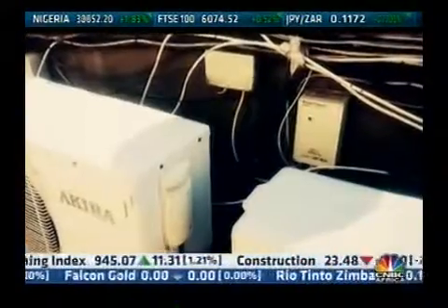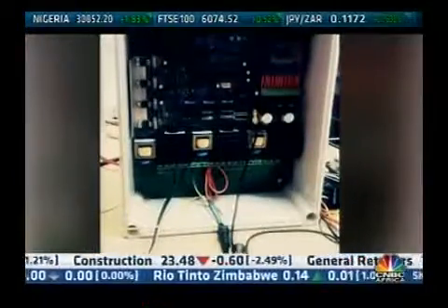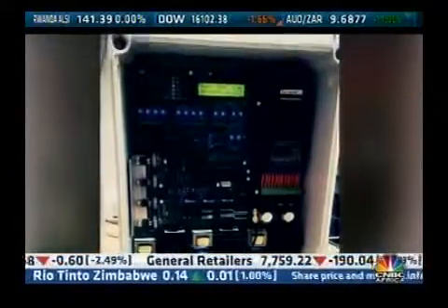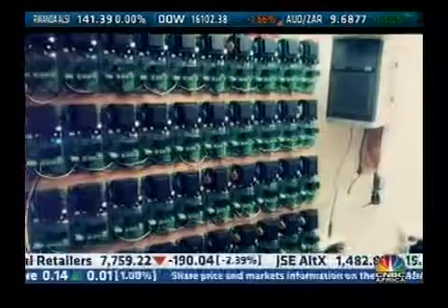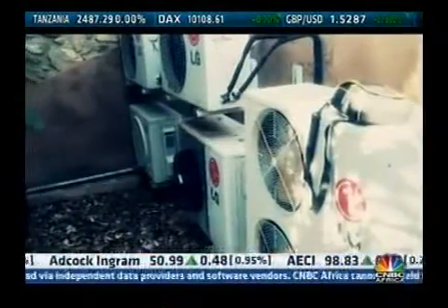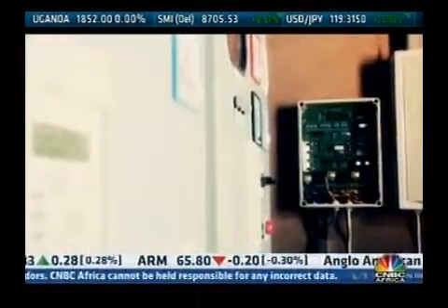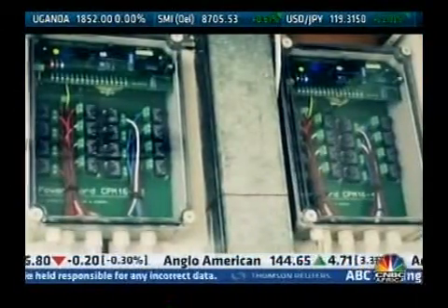And then when that power approaches a preset limit that you're managing it at, the system will start shifting loads. What is meant by that is we manage what we call non-essential loads, things like geysers, air conditioners, underfloor heating, boilers, and those sorts of loads. They have some inertia in them so that they don't have to all run exactly at the same time.